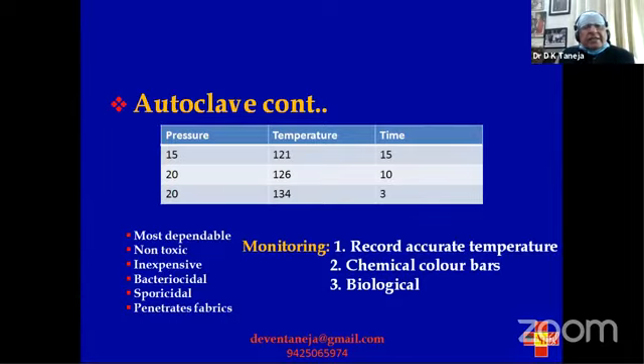So we see that it is very dependable, non-toxic, inexpensive, bactericidal, sporicidal, and it penetrates into any type of fabric. What is important is that you must do the monitoring very properly, so that your autoclave is working accurately. You have to record the temperature, which should give you an accurate reading. Number 2, we put chemical color bars, which change color once the things get sterilized. You must check that.